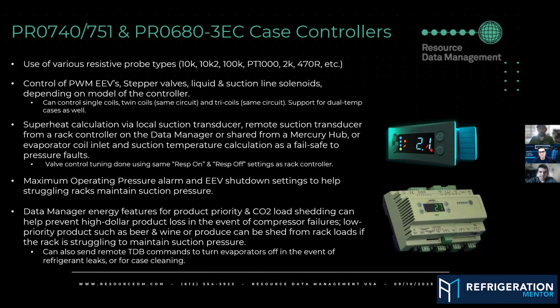There's also features in the data manager I want to get into for product priority and CO2 load shedding. So for product priority, when you have a pressure event where your suction pressure, maybe it goes too high, maybe you've got a run proof as well, you can go off various different fail conditions. You can actually shut all of the valves on all of your controllers until this condition has kind of remedied itself, and then it will start staging cases back on by priority. If you have ice cream on a low temp group, that's going to be really high priority. You're going to want that running before maybe like a frozen bakery case that doesn't have as much valuable product in it.